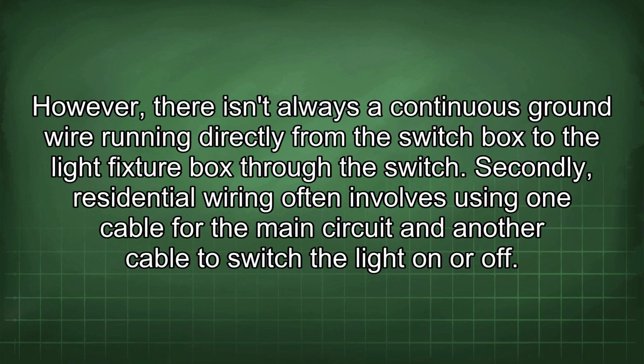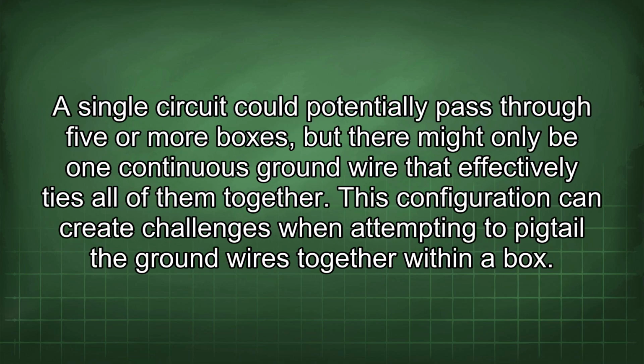However, there isn't always a continuous ground wire running directly from the switch box to the light fixture box through the switch. Secondly, residential wiring often involves using one cable for the main circuit and another cable to switch the light on or off. A single circuit could potentially pass through 5 or more boxes, but there might only be one continuous ground wire that effectively ties all of them together. This configuration can create challenges when attempting to pigtail the ground wires together within a box.